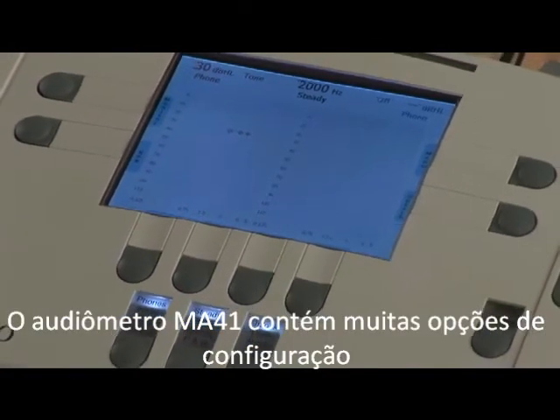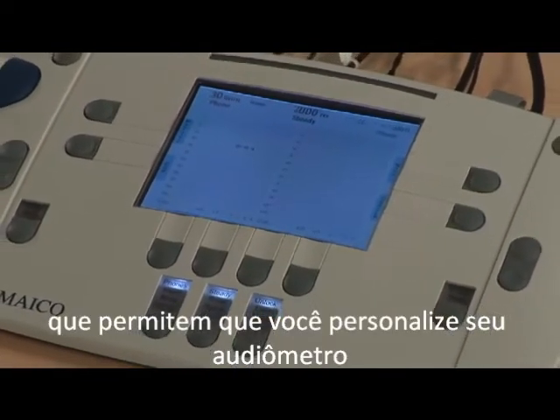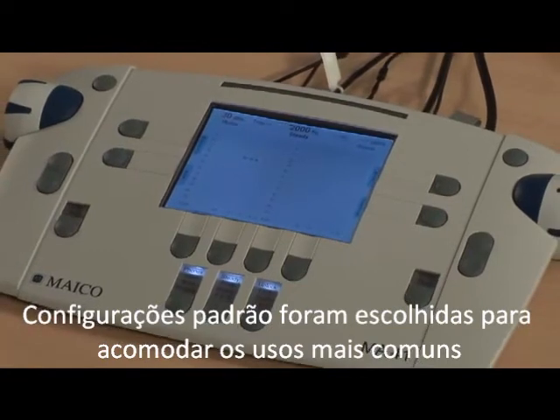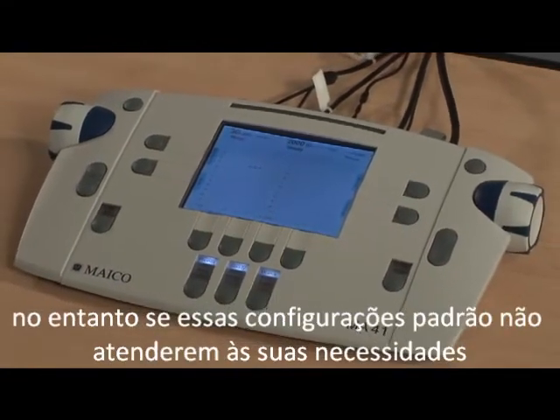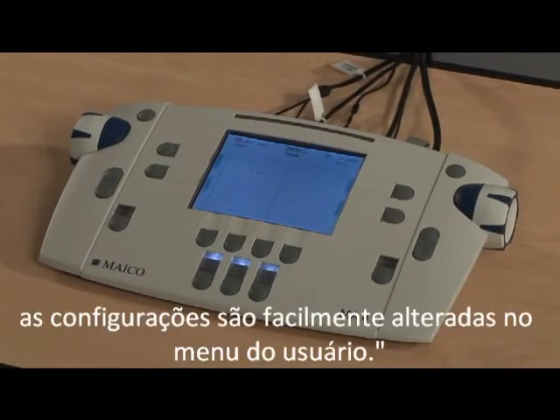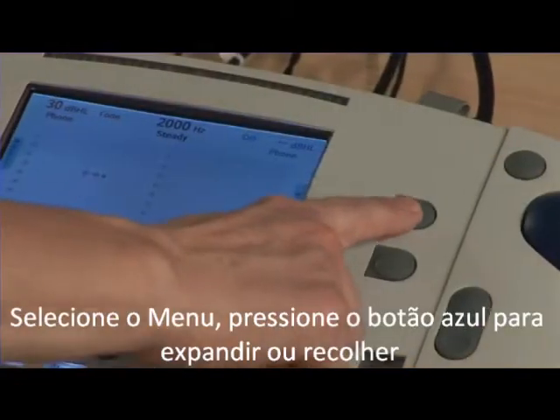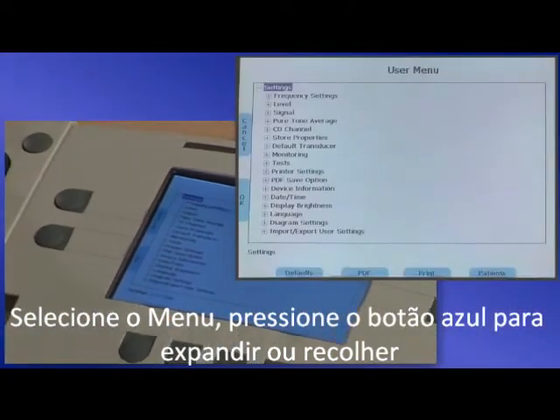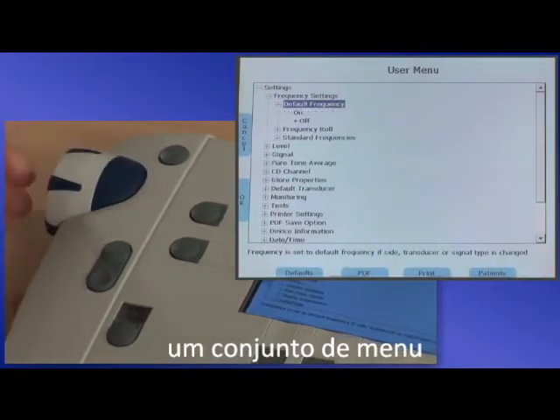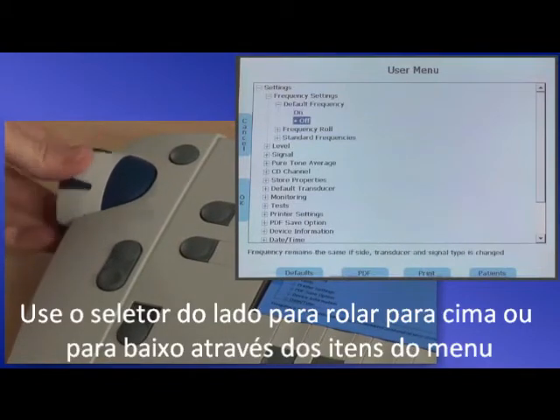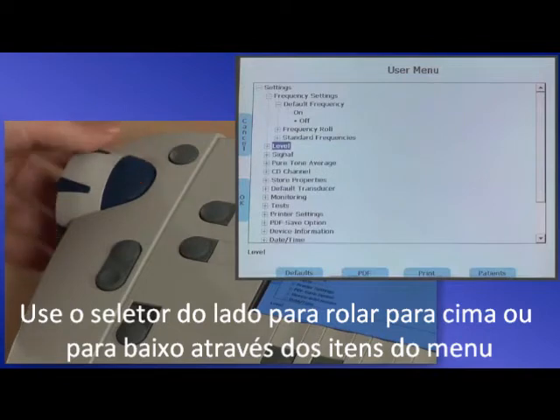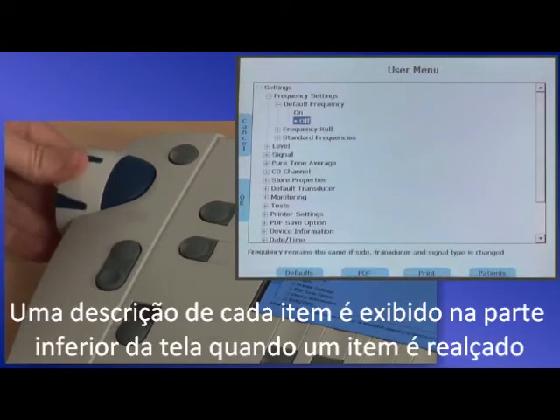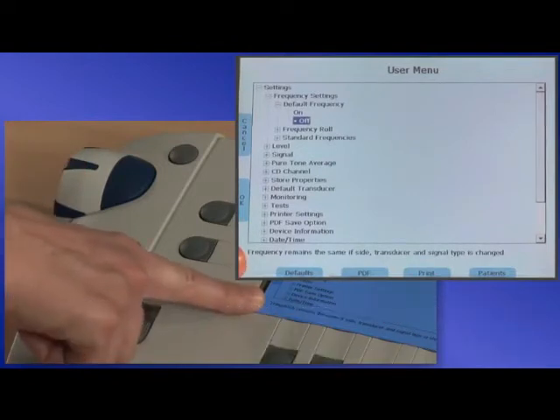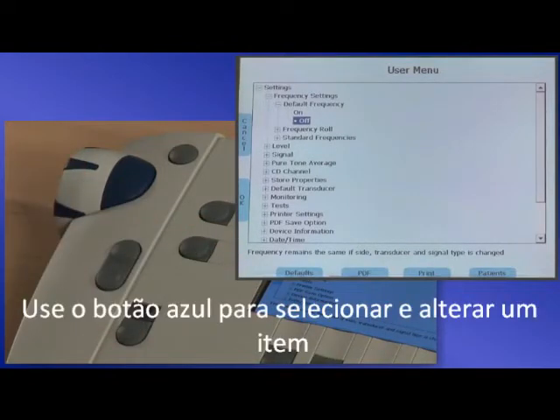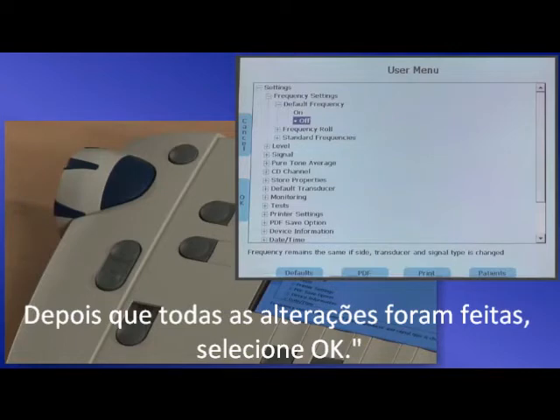The MA41 audiometer contains many setting options that allow you to customize your audiometer. Default settings have been chosen to accommodate the most common uses. However, if these default settings do not meet your needs, the settings are easily changed in the user menu. Select Menu. Press the blue button to expand or collapse a menu set. Use the side dial to scroll up or down through the menu items. A description of each item is displayed at the bottom of the screen when an item is highlighted. Use the blue button to select and change an item. After all changes have been made, select OK.